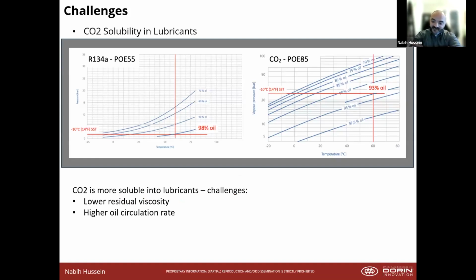We said lubrication was a challenge, and that's because the oil that we use for CO2 compressors, the CO2 is very soluble in it. So where you would see an R134A in a POE 55 system, you have 98% oil with 2% mixed in. But with CO2 and POE 85, you have about 93% oil. That's 7% of the CO2 dissolved into it. That leads to lower residual viscosity of the oil, less of it being able to lubricate the system. It leads to the higher oil recirculation rate. But the main thing is CO2 is a detergent. So if you have liquid CO2 inside of your oil and it goes upon any metal surface, it's going to clean it. And now you have metal to metal.